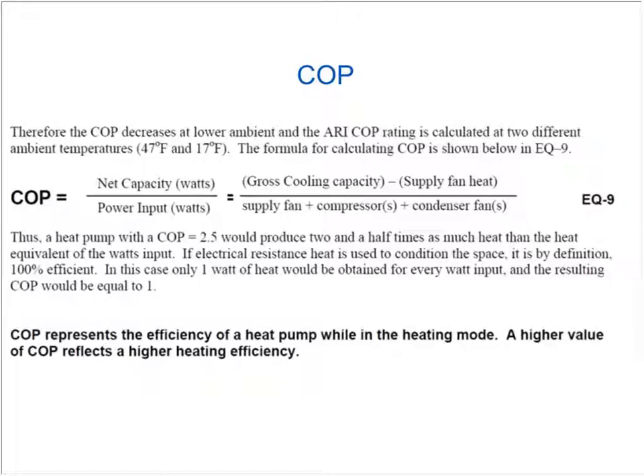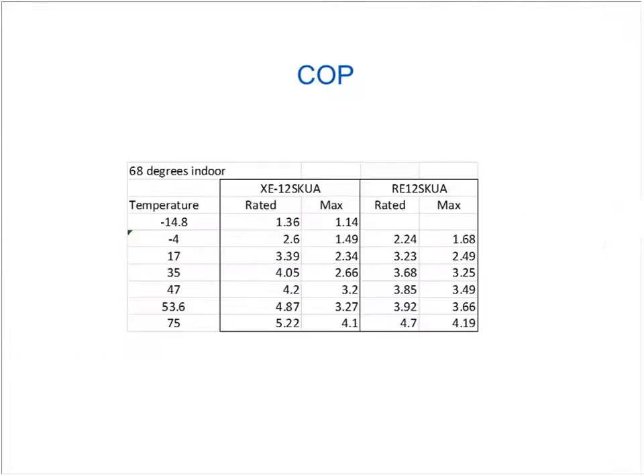COPs are an interesting function, and what happens with the COPs is that they'll tend to lock down the condenser, and it's kind of a disadvantage for ductless heat pumps, because we're using an ECM motor that can move up and down through the continuum of speed and output. But to measure a COP value, you simply have to lock that down so that the heat pump doesn't go up and down. So I'll give you kind of an example here, I think.